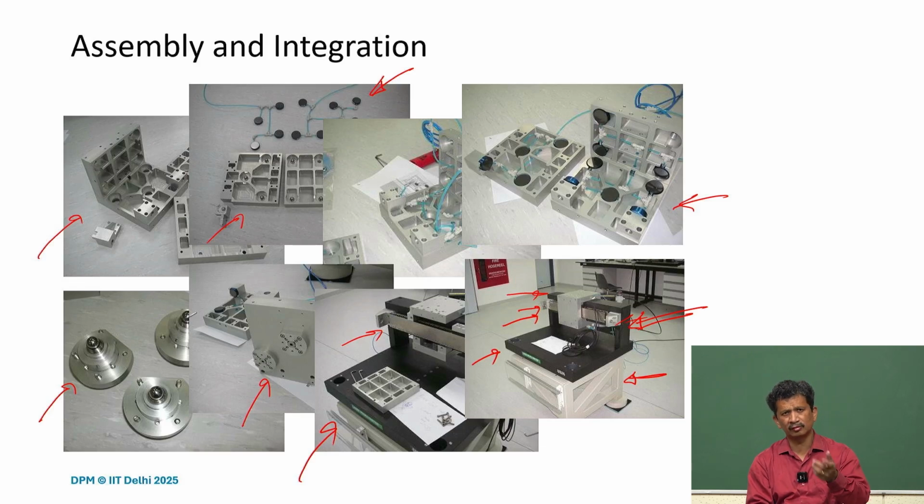And once it's done, and once you activate it, once you supply the air pressure, you find that it's so nice, because the flooring is also not a rigid floor, it's specially made flooring, so that the ground vibration should not pass to the system. So once you step into the area, actually it deforms. So even at 1 degree of tilt, it will start sliding towards one side. So you can just poke it with a finger and it starts moving.